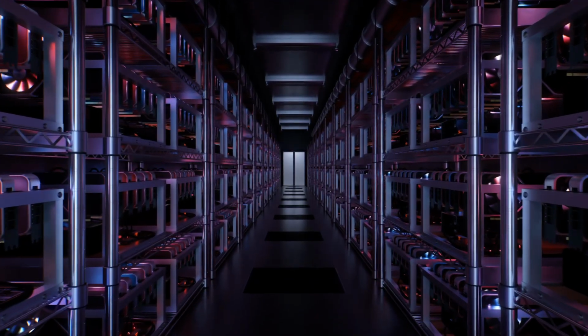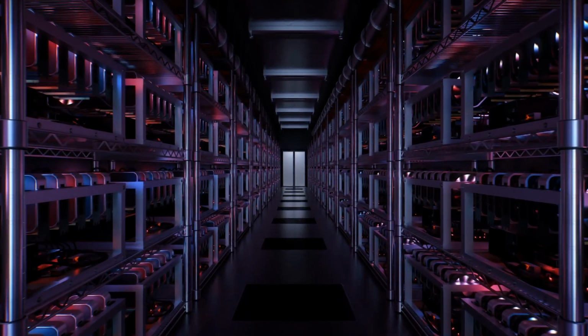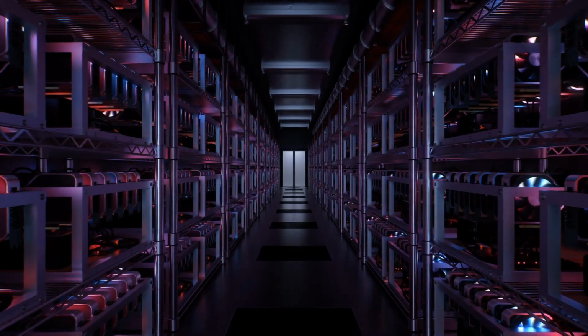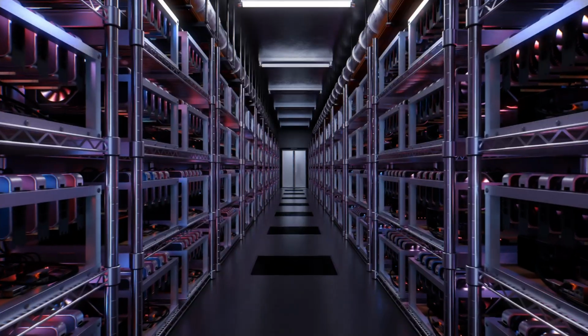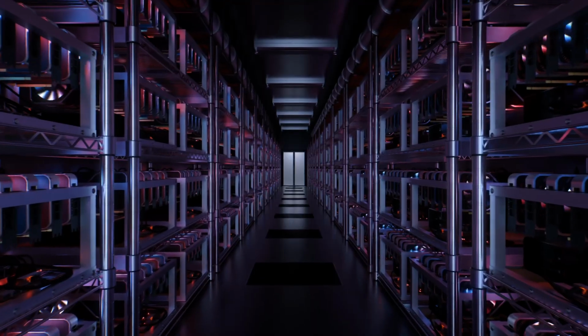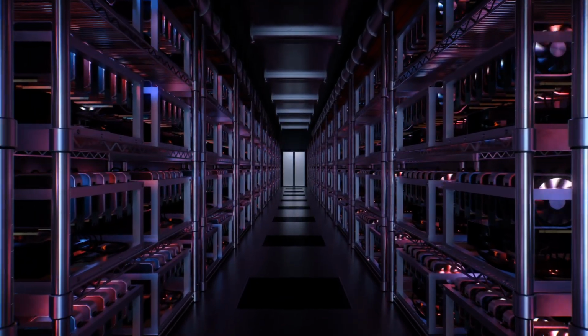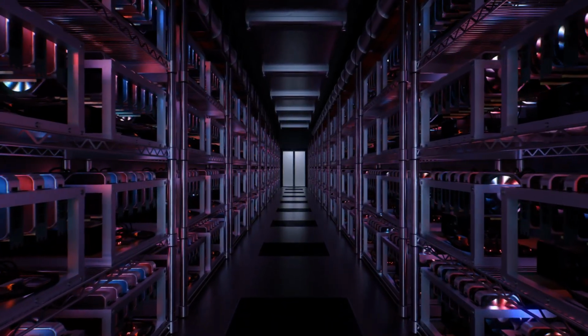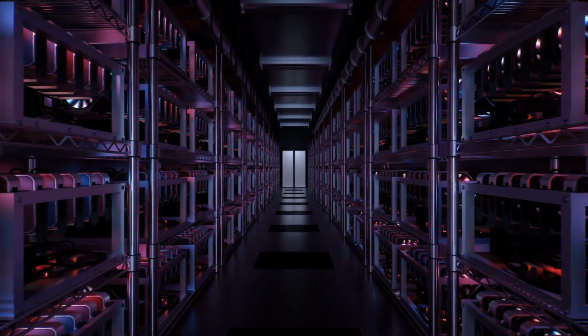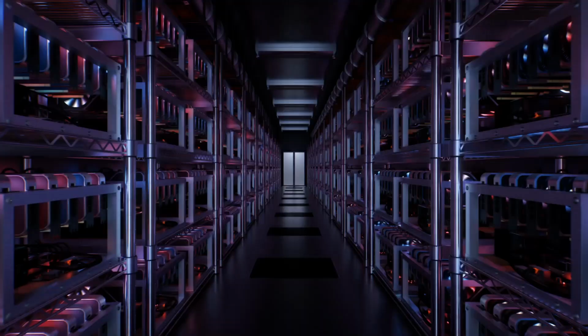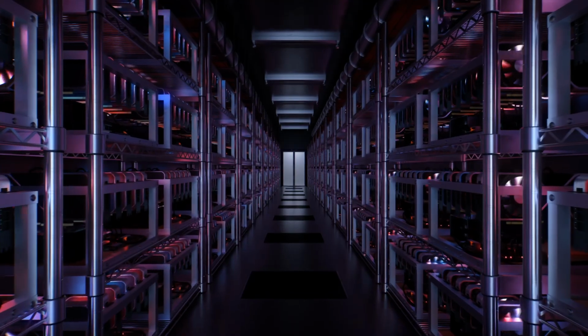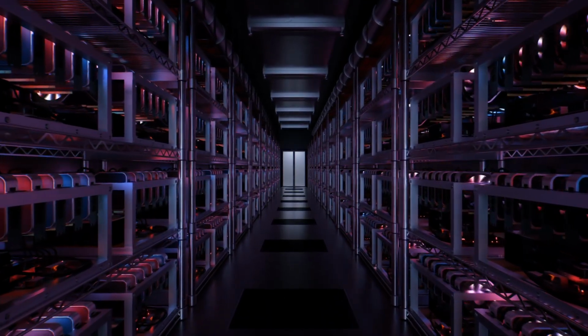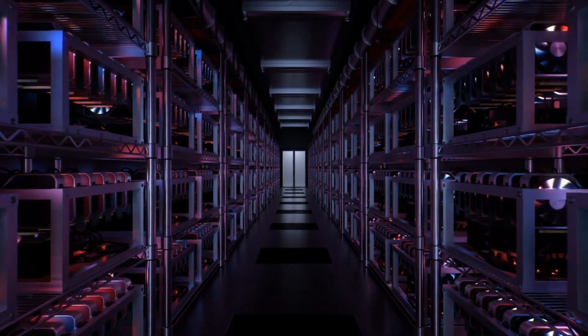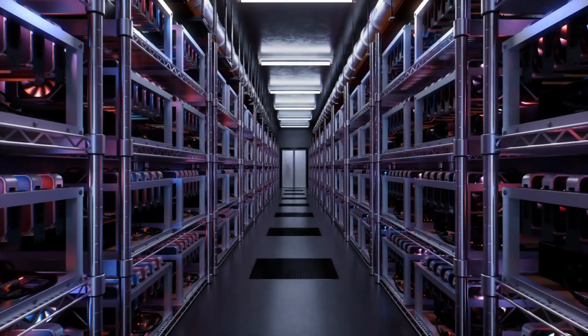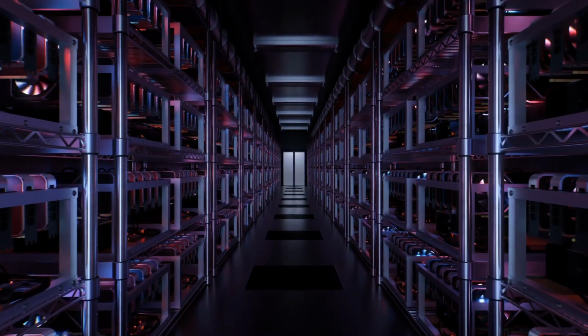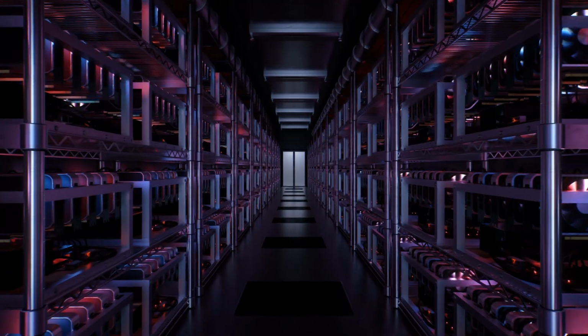Exactly. And speaking of visibility, the granularity of what SEC monitors is frankly obsessive. The telemetry and analytics list includes temperature, pressure, flow rate, water quality, leak detection, and power consumption. It's functioning like a critical care monitor in an intensive care unit, but for fluid dynamics. It really is. But the control aspects are just as specific. The software dynamically manages pump speed, primary side valves, and condensation.